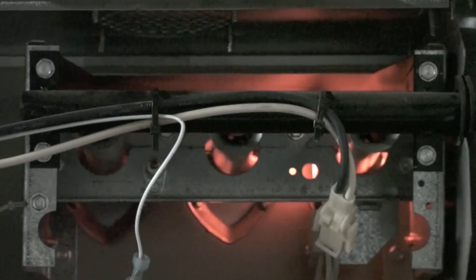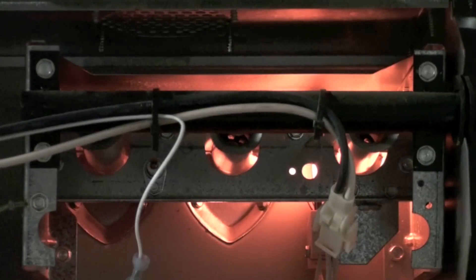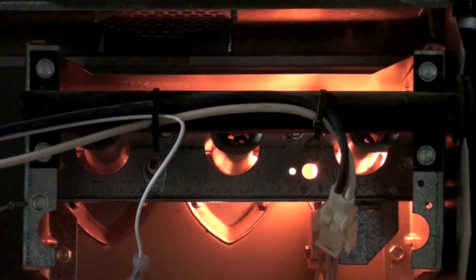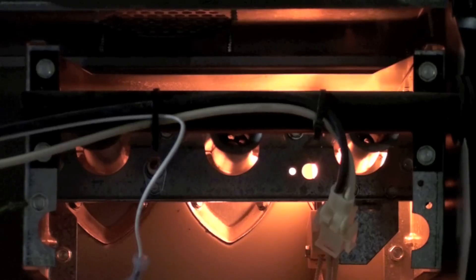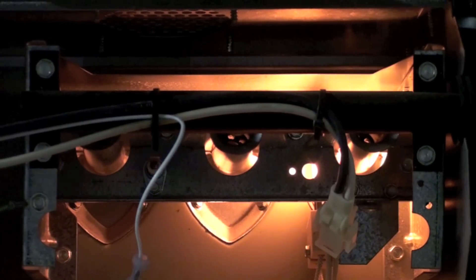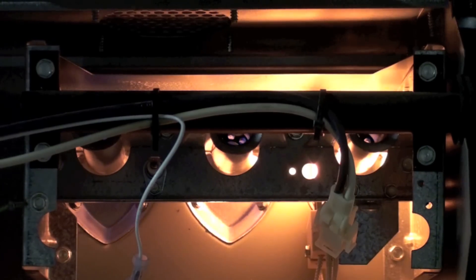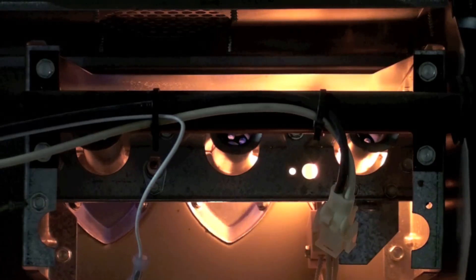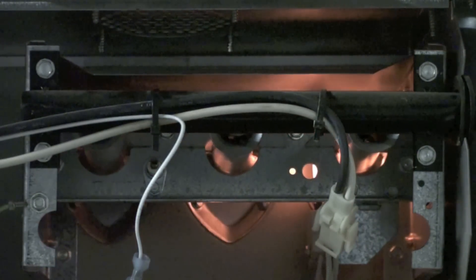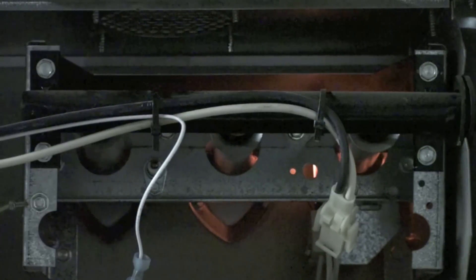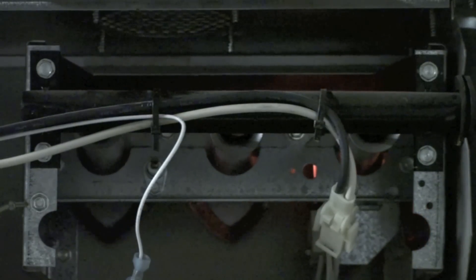Okay, here comes the hot surface igniter again. There it goes, burners are on. Okay, if that's your symptoms, good chance you've got a dirty flame rod.